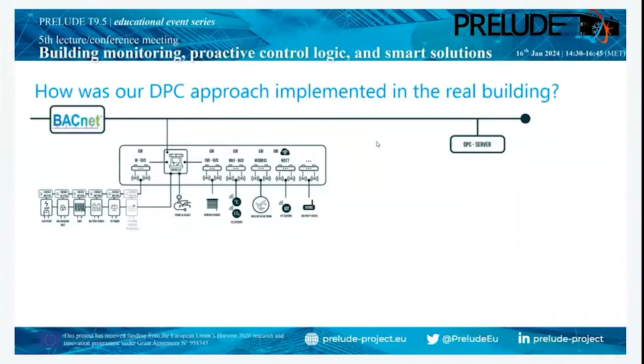How was our DPC approach implemented in the real building? We have a building automation and control network, and therefore we also have a BACnet OPC server, and we used MATLAB with an OPC toolbox, so we can read values from the BACnet to the workspace in MATLAB. We can make our calculations and optimization in MATLAB, and the output of the optimization is the control input, which we will write in BACnet. So we will write to the heat pump that it should be switched on, and also that the floor heating system in zones A, B, C, and so on has to consider the power that is the outcome of the optimization algorithm.